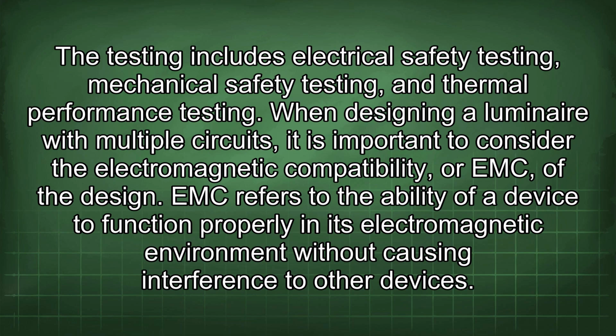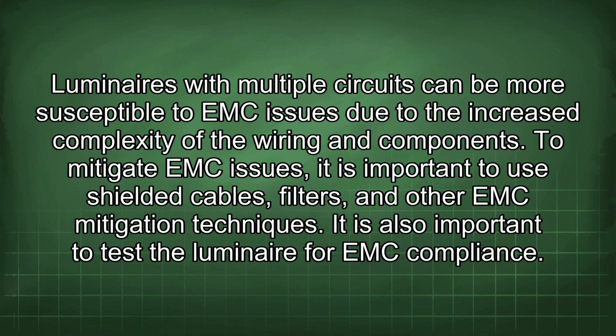When designing a luminaire with multiple circuits, it is important to consider the electromagnetic compatibility, or EMC, of the design. EMC refers to the ability of a device to function properly in its electromagnetic environment without causing interference to other devices. Luminaires with multiple circuits can be more susceptible to EMC issues due to the increased complexity of the wiring and components. To mitigate EMC issues, it is important to use shielded cables, filters, and other EMC mitigation techniques. It is also important to test the luminaire for EMC compliance.